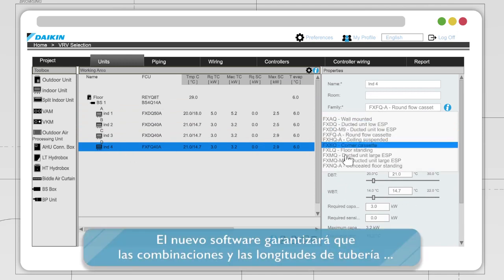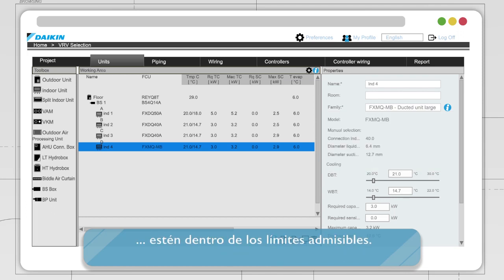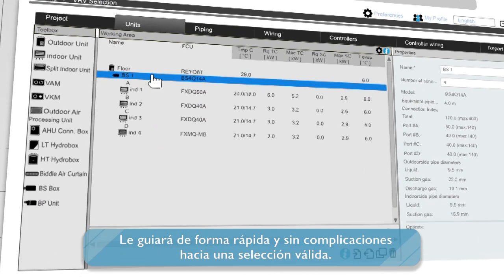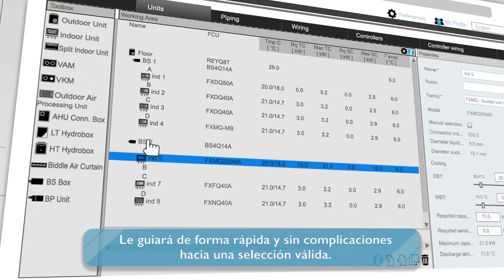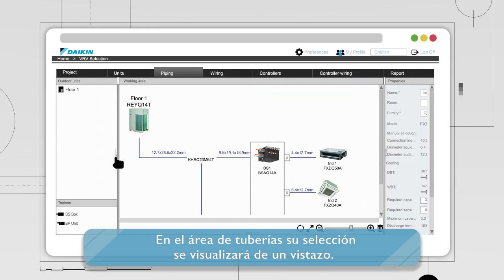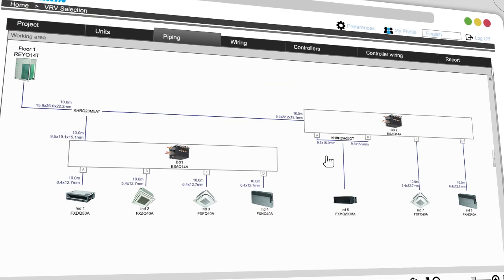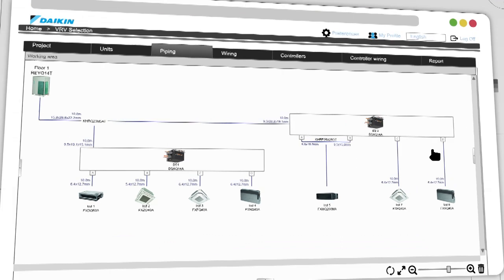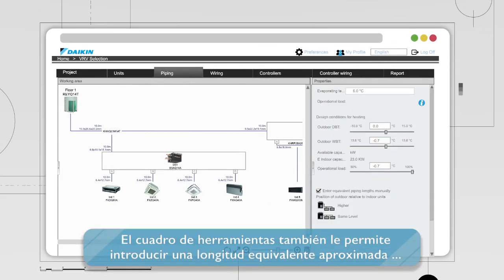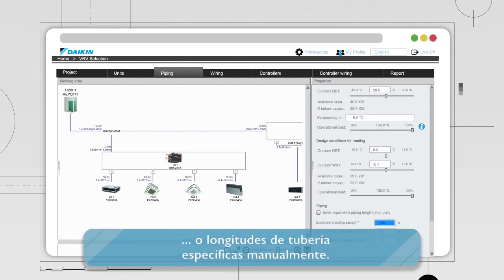The new software will assure that combinations and pipe lengths are within permissible limits. It will guide you fast and hassle-free towards a valid selection. In the piping area, your selection is visualized at a glance. You can zoom in or out or go to full screen mode. The tool allows you to enter a rough equivalent length or specific pipe lengths manually.